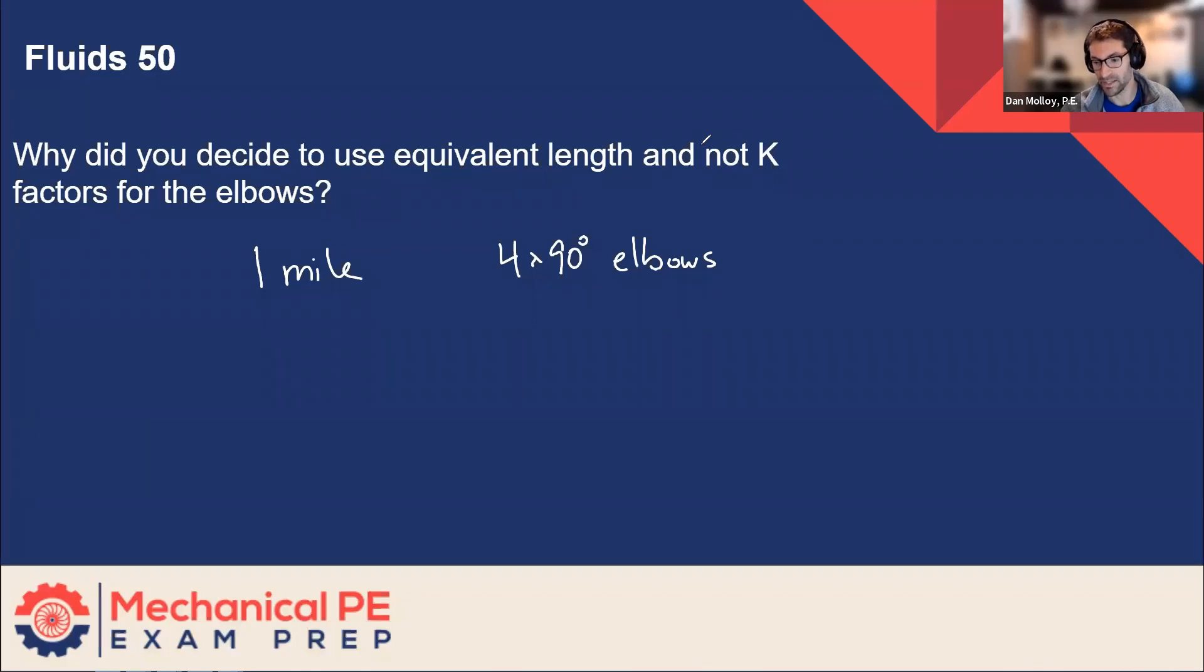I did a rough calculation and the minor loss is about two percent of the total losses. But that's a non-answer because your question is why do the equivalent length and not the K factors.